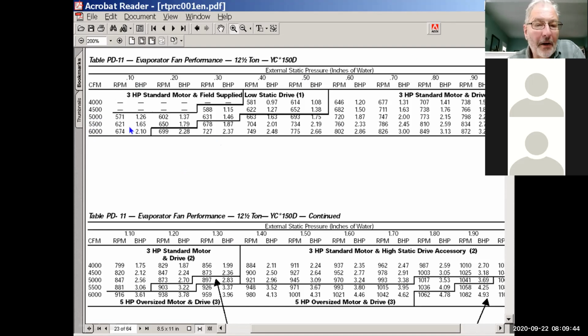If you look at the chart, anything under about a 0.3 static, we're looking at low static drive here. I mean, we don't need that blower doing a whole lot of work. It doesn't need to move all that fast. When we get to like 0.4 or above, now we're looking at the standard motor drive. So typically on a rooftop, if it's a 0.4 static, and we can take that all the way up to about, let's see, 1.2 static, we're looking at that standard drive, okay?